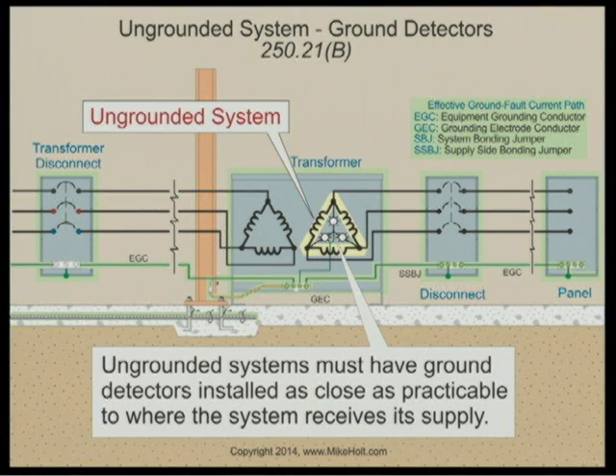At that point, the insulation can't sustain it, and you get a discharge. And more than likely, it doesn't even have to go that high. You start getting motor windings, relays, and electronic equipment, where the tolerances are much closer. So there's just an inherent problem with overvoltage and equipment failure for ungrounded systems. Now let's take a look at the code.